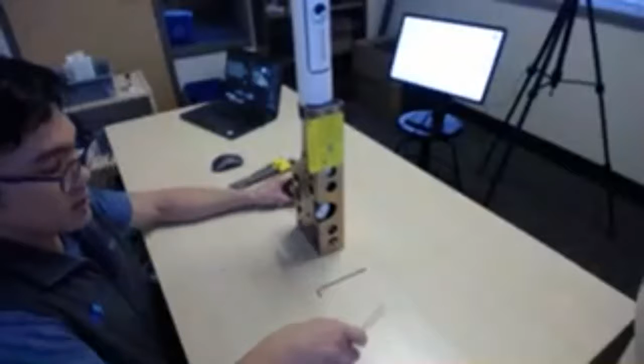remove the dummy block that's currently taking the place of the pH sensor. And when I do this, I like to loosen both screws alternately a little bit at a time, maybe a couple of turns, just so that it's not canting to one side. And then when I'm fully out, you can just pull this straight out, just like that. Okay, so now we can see the female connector inside of the HydroCAT EP. I might need a little bit of light here. So we can see, hopefully, kind of hard with this camera angle, the connector inside of the HydroCAT EP, as well as the part of the flow path that connects to the HydroCAT.